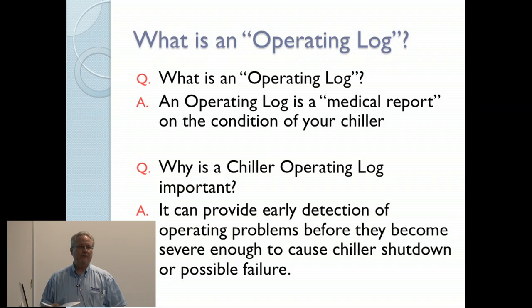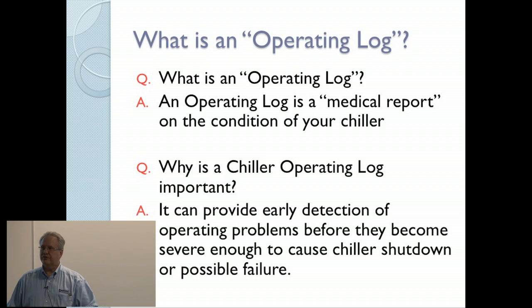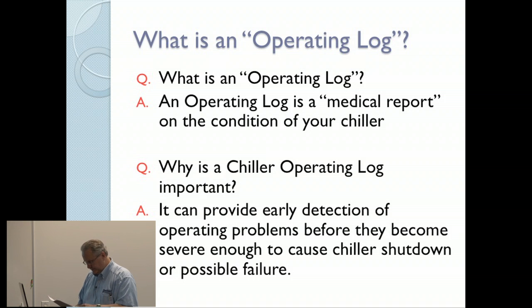Same is true for chiller operating logs. If a tech goes out there who knows how to interpret these logs, and he's out there doing the initial startup for the summer or for the spring, he's logging usually a lightly loaded chiller. But boy, if he was out there in July and August, he'd be logging a totally different chiller under full load. And there's a lot of value to that. A lot of people choose not to invest in that summer inspection, that is something I think is worthwhile. So just for what it's worth.